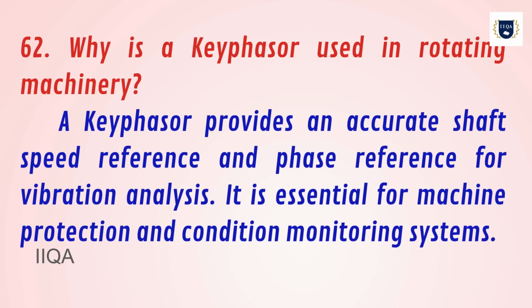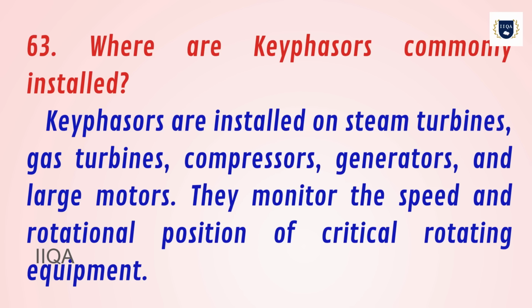62. Why is a Keyphasor used in rotating machinery? A Keyphasor provides an accurate shaft speed reference and phase reference for vibration analysis. It is essential for machine protection and condition monitoring systems.